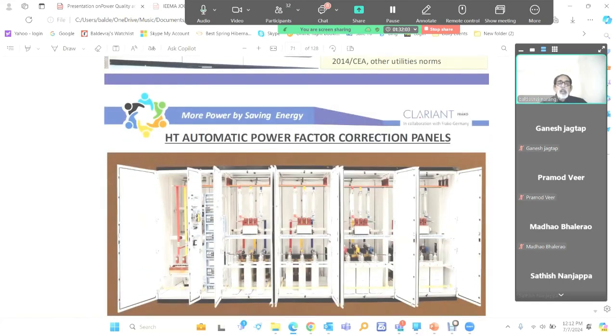Then these days, earlier we used to have only automation at low voltage, APFCs. But now we have APFC at even up to 33 kV. So the switching is done through a vacuum contactor. Earlier we used to have only fixed capacitors at high voltage. So now we can have APFCs. Vacuum contactors can be used for switching capacitors.